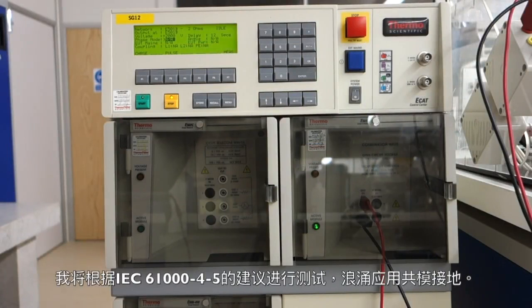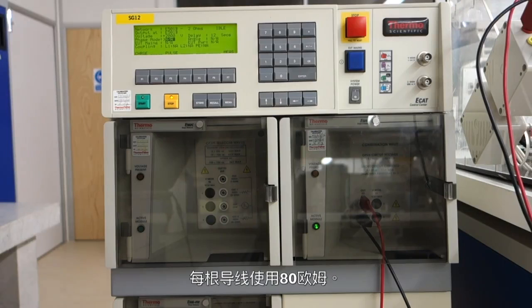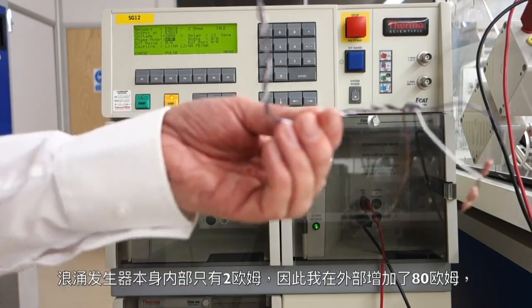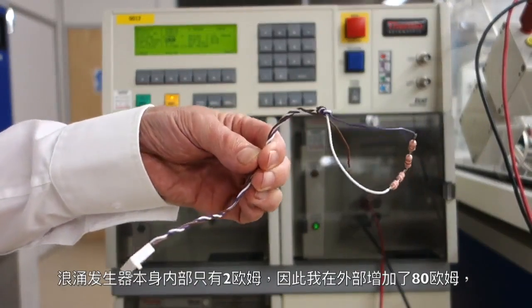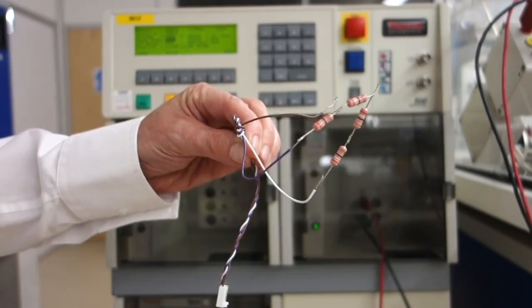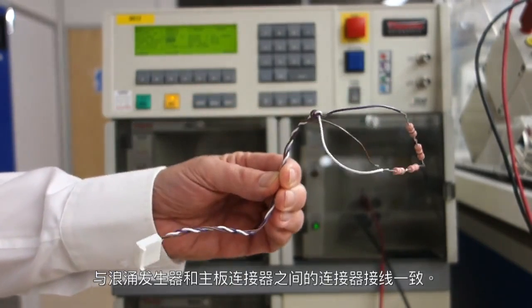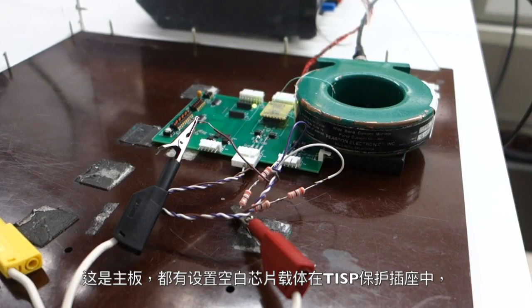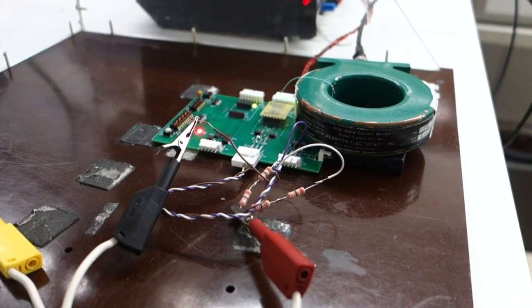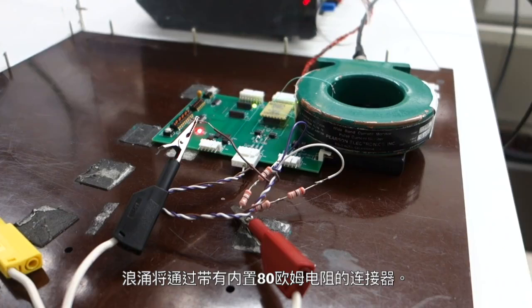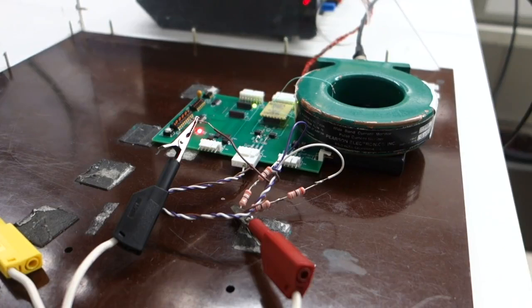I'm going to do the test according to IEC 61000-4-5, which for symmetrical lines like RS-485 suggests that the surge is applied common mode with respect to ground, with 80 ohms in each wire. The surge generator itself only has 2 ohms internally, so I've added the 80 ohm resistance externally in line with the connector wiring between surge generator and mainboard connector. Here's the mainboard all set up, with the blank chip carrier in place in the TISP protection socket, and with the current coil monitoring the current. The surge will be applied through the connector with the inline 80 ohms resistors.